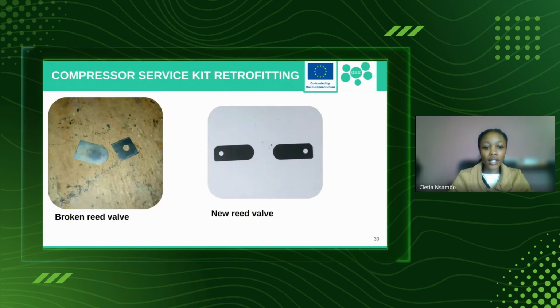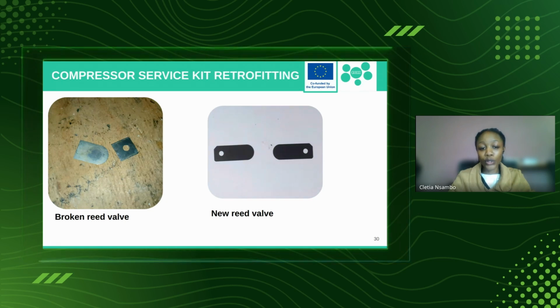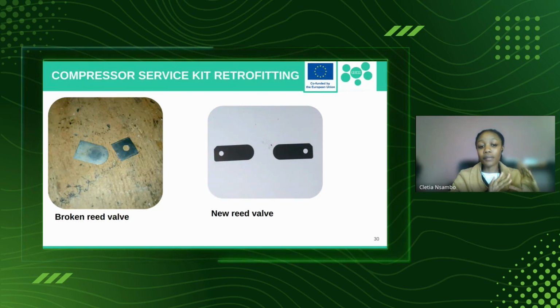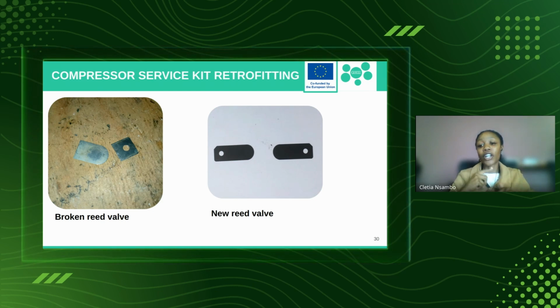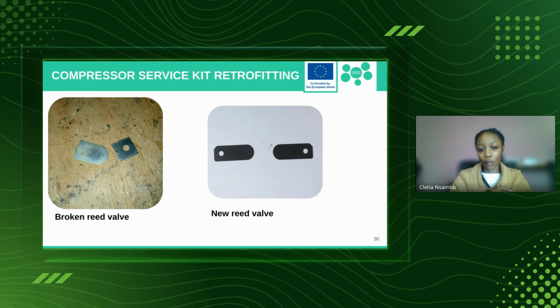Another problem we face when servicing compressors is broken reed valves. When replacing reed valves, if you're using one from a different compressor model, you have to make sure the hole on the reed valve matches the screw size of the one you're replacing, and that the dimensions of the reed valve fit perfectly on the hole that lets air in or out of the compressor.